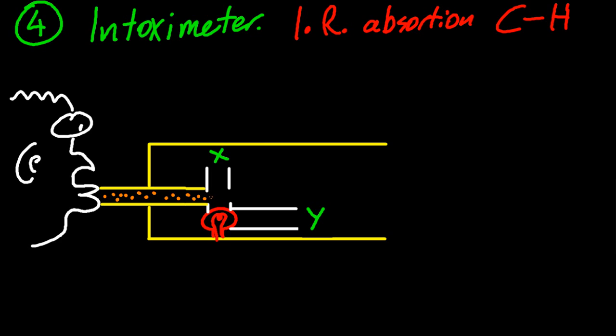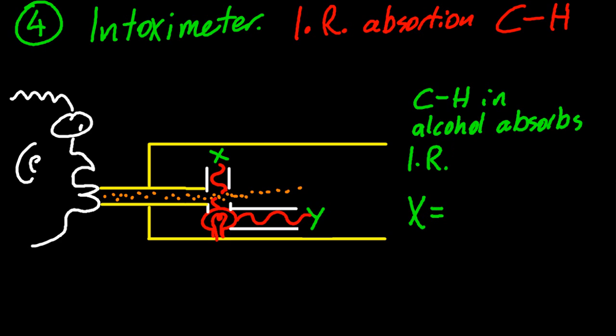So infrared light of a certain wavelength will be absorbed by the carbon-hydrogen bond in alcohol. So if I breathe through there, through the machine, what the machine's going to do is it's going to compare the light that hits Y with the light that hits X. Now the carbon-hydrogen bond in the alcohol absorbs some of this infrared radiation. Now if X equals Y, if the light's the same at both places, there's no alcohol in your breath. Well, you should be able to see where this is going now.